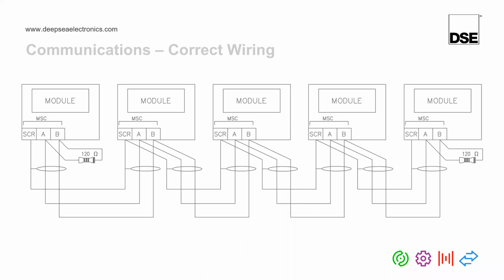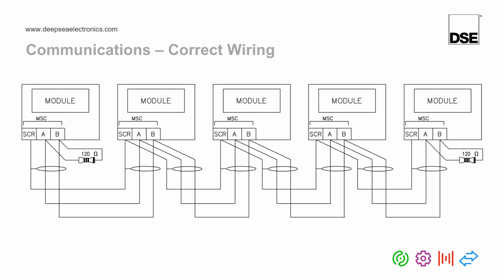The next most common problem we come across is wiring of the MSC link. On the board here, you can now see how the MSC link should be wired. You can see it's wired in what we call a daisy chain type arrangement, where we have wires going into the module and out of the module, into the module, out of the module. You can also see there is a 120 ohm termination resistor at the start of the cable and the end of the cable. It is very important that you wire the MSC link in a daisy chain configuration like shown here, and that you also put in a 120 ohm termination resistor at the start and end of the cable.